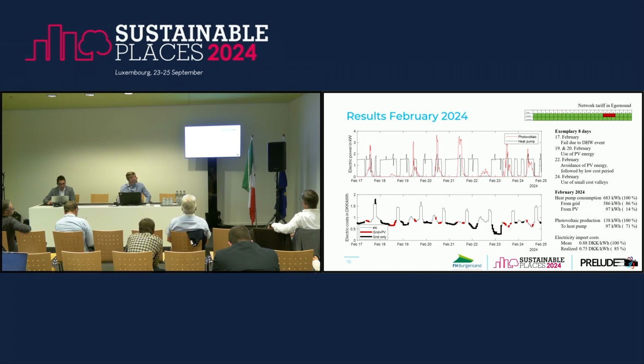Also quite interesting, if you take a look at February 22: during the day there's a little photovoltaic energy, but the controller foresees that on February 23 at night there will be very cheap electricity from the grid. So it avoids using the photovoltaic electricity and waits for the cheap grid electricity instead. In the night between the 22nd and 23rd, it consumes electricity from the grid for several hours because it was cheaper than the photovoltaic electricity. On the 24th, for example, you see the small values, so it's quite accurate.